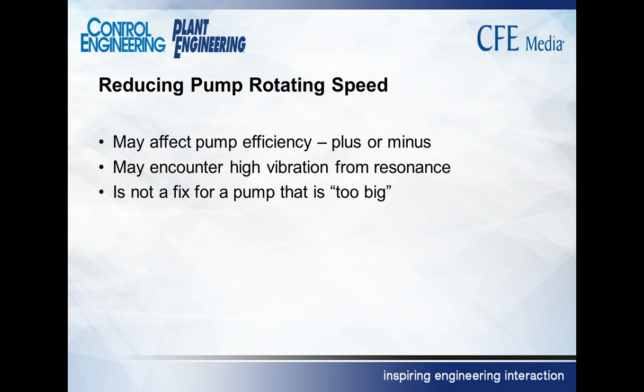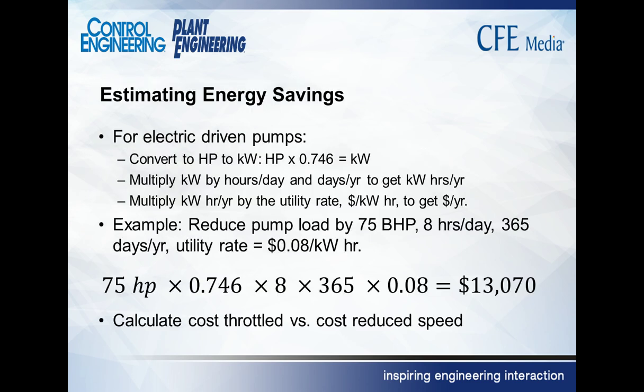One of the other impacts of reducing the speed: all machine structures have frequencies they like to shake at, called natural frequencies. And if you slow the speed of the pump down until some component of that pump excites a natural frequency, you have resonance and you're going to have high vibration. If you're going to be adjusting machine speeds, you should be prepared to deal with possible mechanical issues with vibration. And if you have a pump that's too big, like the one we saw before, operating very close to its allowable operating range, slowing that pump down will not fix that problem. If a pump's too big, the only real solution is to replace it with a smaller pump that operates closer to its best efficiency point.